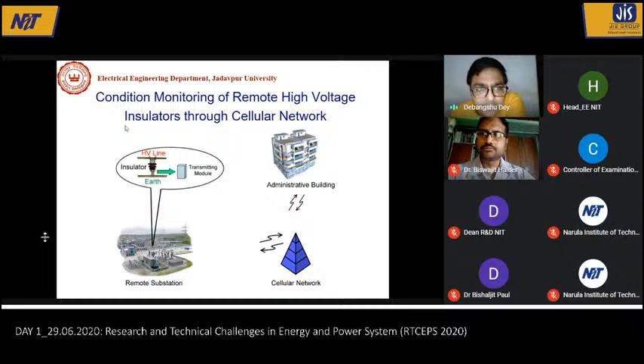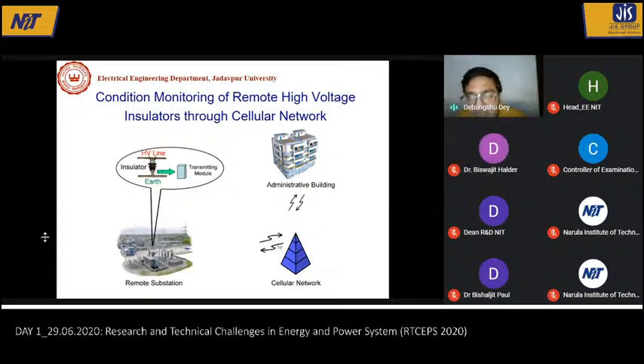So if we can monitor the condition of the insulator before total breakdown, we can identify its condition, and then we can replace that faulty or aged insulator in time, so that we can prevent failure of the network. So the idea is there will be some modules we can install in the insulators, and from that module we can transfer the data using the cellular network to the control, administrative, or analysis building.